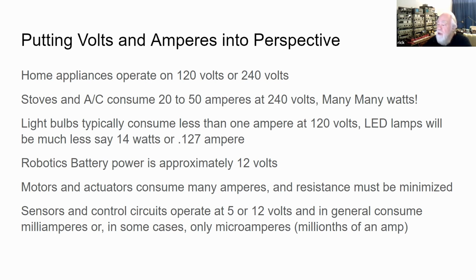Sensor circuits consume extremely small amounts of power, thousandths of an ampere, or milliamperes, or even microamperes in other cases. The wire size needs to be large enough that we don't damage it while working on it, but a hair-fine wire is big enough to carry these signals between devices, and sensors operate anywhere between 5 and 12 volts.